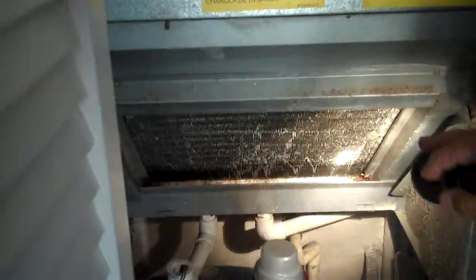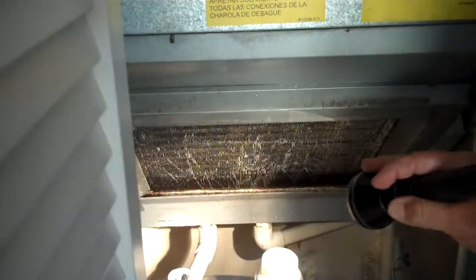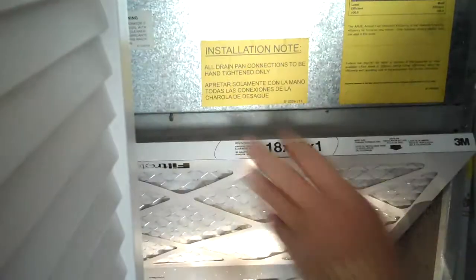We want to check the filter here and make sure that the evaporator coils are clean, and the water is draining well. You've got your condensation line going out of here with a float switch. We'd also be pulling temperatures on the heating and cooling on this to make sure that it's working properly.